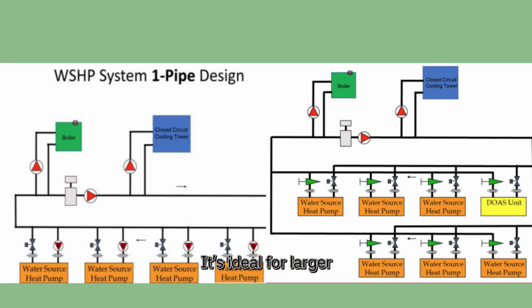It's ideal for larger or multi-story buildings where consistent performance and temperature control are critical. Finally, there's direct versus reverse return piping. A direct return route sends water back along the shortest path, which can lead to uneven flow. A reverse return layout balances this by ensuring each WSHP has equal piping length, resulting in better flow balance and overall system stability. In short, one-pipe systems are simple and economical, while two-pipe systems with reverse return offer superior balance and efficiency for larger installations.